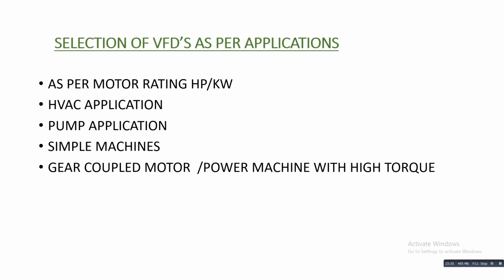Okay, now the main thing is, before selecting the VFDs, you have to make sure of some points. If you want to buy a VFD for your application, make sure that the rating is as per your equipment. Whatever equipment rating is mentioned, you have to go with the same rating of the VFD. You can go for a higher rating VFD also, but a lower rating VFD than the equipment is not possible. So you have to make sure of the ratings first.